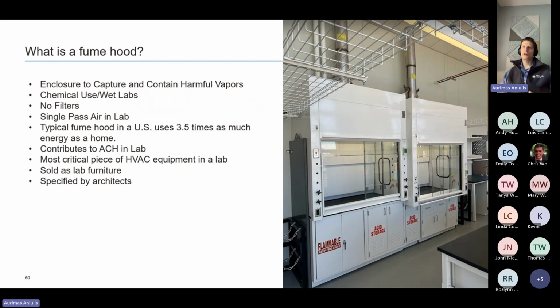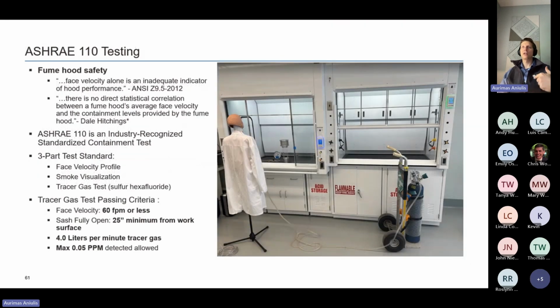And then once you have air in the room and controls on the fume hood, these fume hoods need to go through a commissioning process, which takes the form of an ASHRAE 110 test. Now, fume hood safety was typically defined as face velocity, and the standard, still to this day, people could argue, was 100 feet per minute. Well, in 2012, the ANSI Z9.5 lab standard comes out and says face velocity alone is an inadequate indicator of fume hood performance. There is no direct statistical correlation between a fume hood's average face velocity and the containment levels provided by the fume hood. Boom.